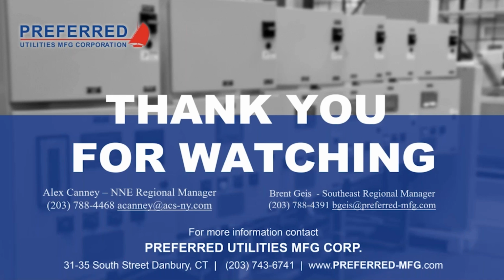Alex, the other thing that we run into, we've spoken a lot about fuel filtration, and when you try to filter fuel, you run out of options with submersible pumps and filters. Positive displacement pumps can filter fuel a lot easier. They have an open drop tube that is pulling fuel through a strainer basket, which is relatively your pre-filter before pushing it through the filter unit, whereas a submersible pump actually has a screen on it.